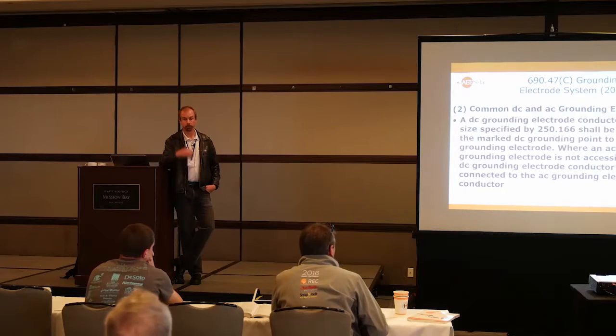2017 code goes back to that initial intent that says, if you've got any structure with PV on it, it's got to have an electrode. If it doesn't have an electrode already on it, then you install one according to Article 250. But it's still got to be wired back to the AC electrode. The equipment grounding conductor must eventually be tied to that electrode system, the local electrode system, and that's the key.